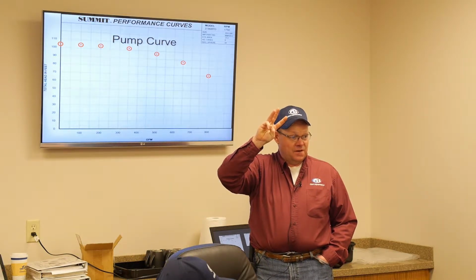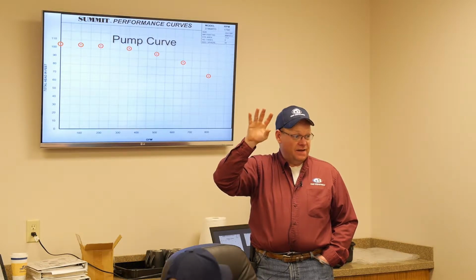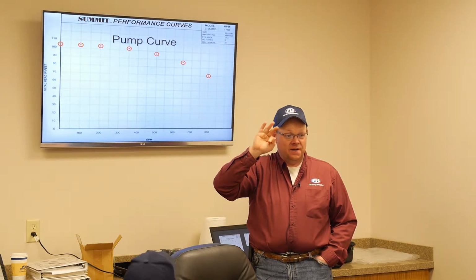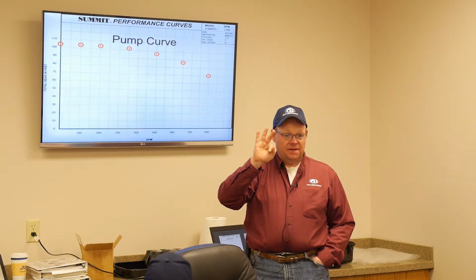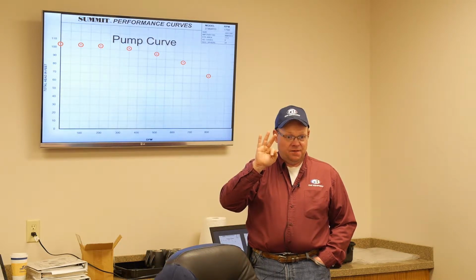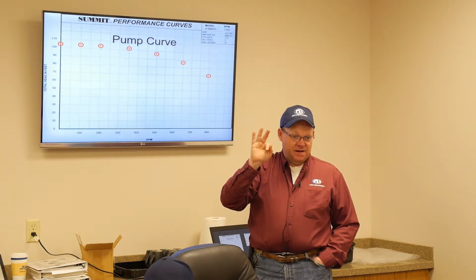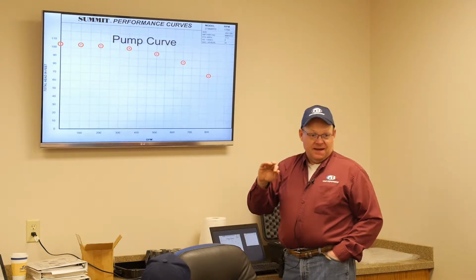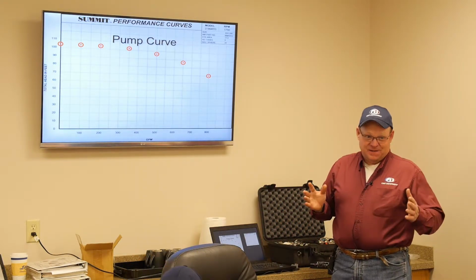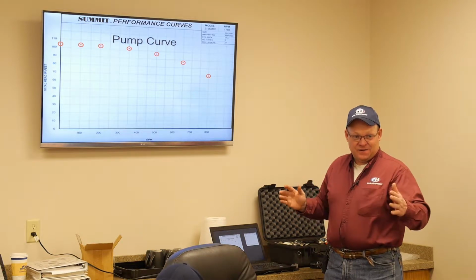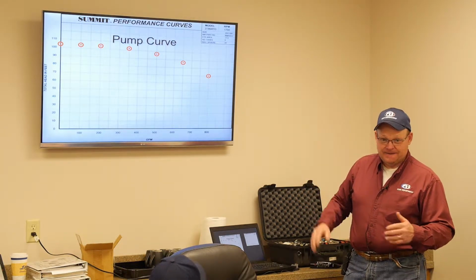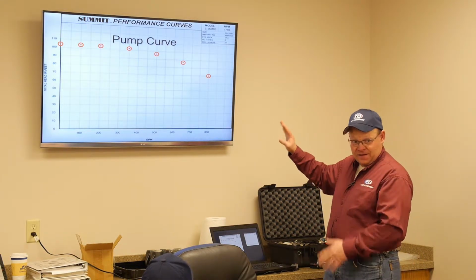So from 500 gallons to 650, we only got 3 pounds difference, but I'm doing 150 gallons a minute more flow. So I'm doing nearly 35-40% more flow with only 3 pounds difference in the performance. Is that kind of registering, everybody? So 3 pounds is not much difference in pressure, but I changed the flow by 150 gallons a minute. Is everybody with me so far still?